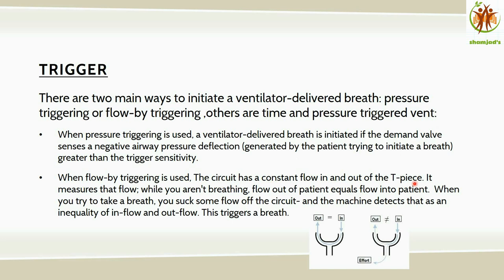With flow triggering, the circuit has a constant flow in and out. The machine measures that flow — when the patient is not breathing, flow out equals flow into the patient. When the patient tries to take a breath, they draw some flow from the circuit, creating an inequality between inflow and outflow. The machine senses this inequality and triggers a breath. You can see in the diagram the continuous inflow and outflow, and how patient inspiratory effort causes the imbalance that triggers ventilation.